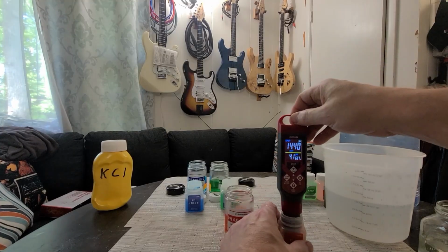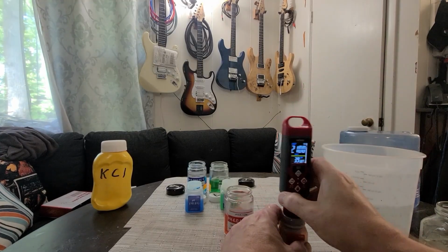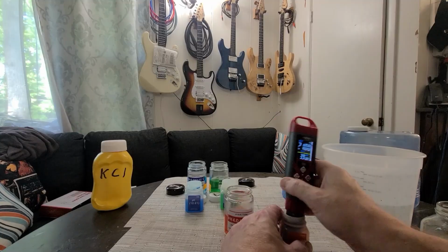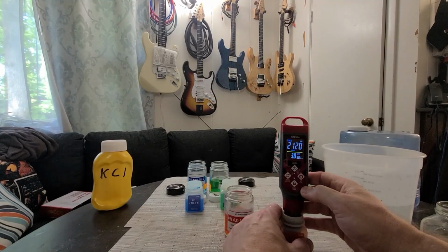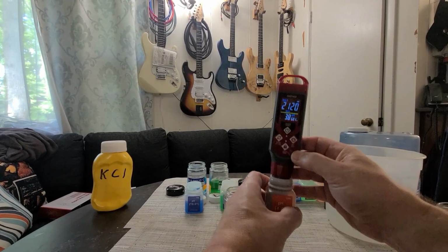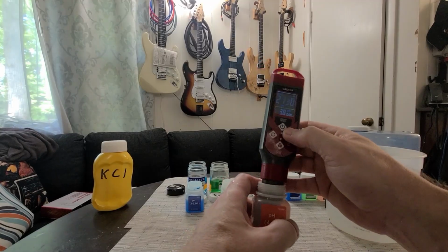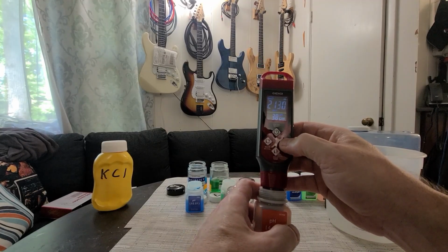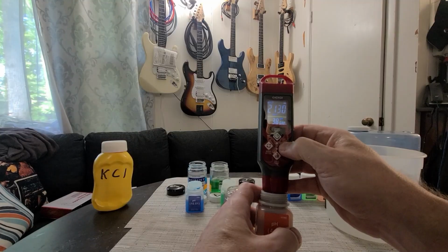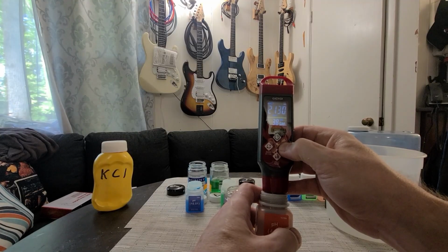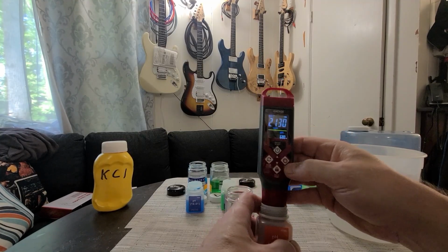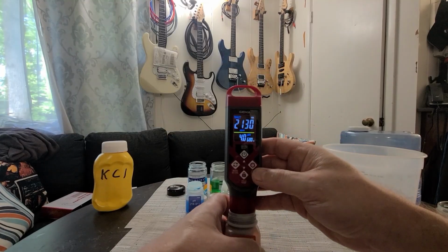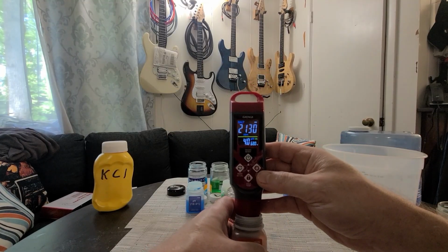Now I go in the actual test solution. Shake it around. Get those air bubbles out. Now here we're going to go 5 seconds on this guy and then let go. 1, 2, 3, 4, 5. Let go. It's flashing. It sees it's 4.0. It says OK.